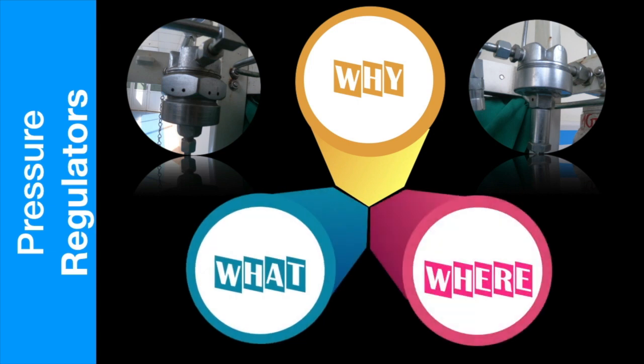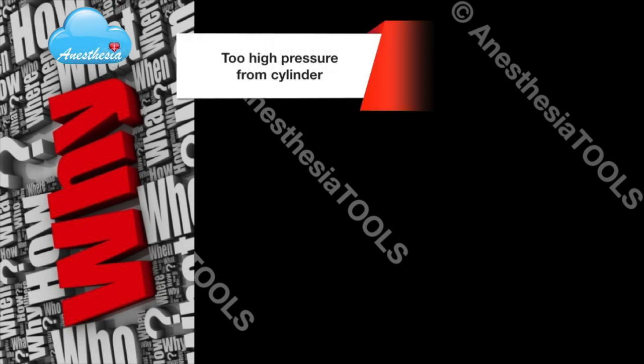Hello and welcome once again to Anesthesia Tools. This edition we'll be discussing pressure regulators in anesthesia machines: why, what, and where. Pressure regulators are used in anesthesia machines for three reasons. One: the pressure delivered from a cylinder is far too high to be used safely in apparatus where a sudden surge of pressure might accidentally be delivered to the patient.